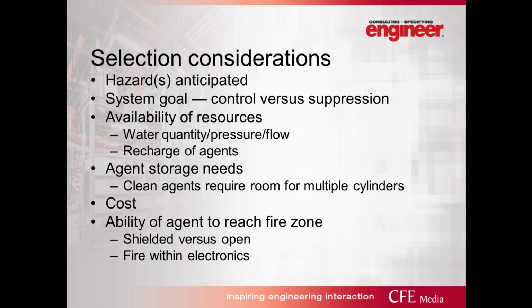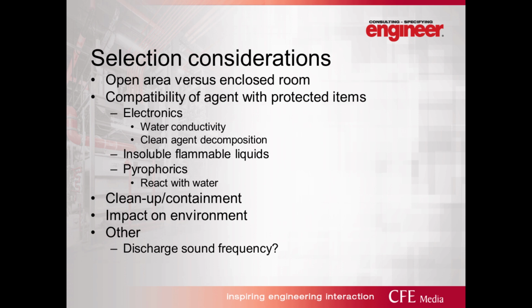Agent storage needs. This comes down primarily to clean agents and inert gases because they are stored in their own cylinders and they must be fairly close to the area where the system is set up. If you are protecting a large enough room, the number of cylinders you need to provide that protection can be fairly significant. Cost is always a consideration, and so is the ability of the agent to reach a fire. Sometimes the combustible loading is shielded by equipment or something else, and again, water application may not be your best way to get the suppression to the source, and you may need to do something else.